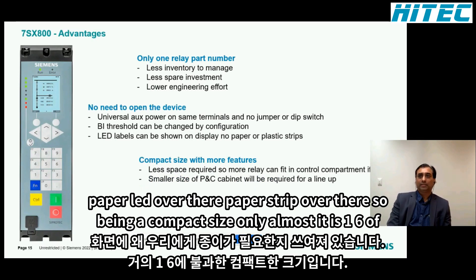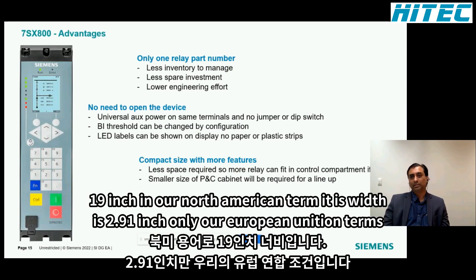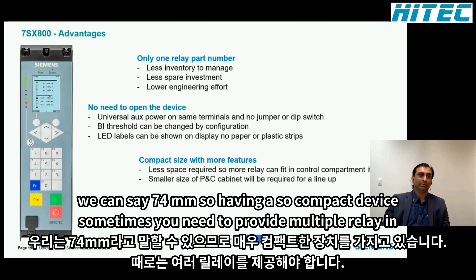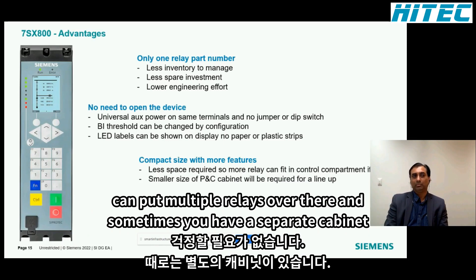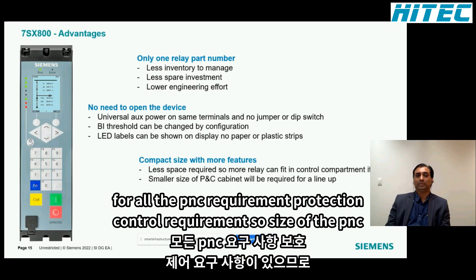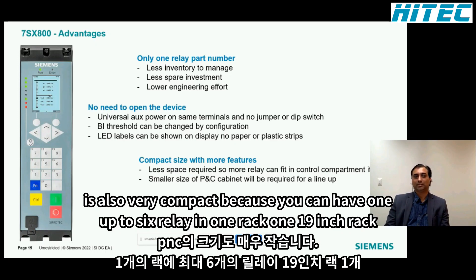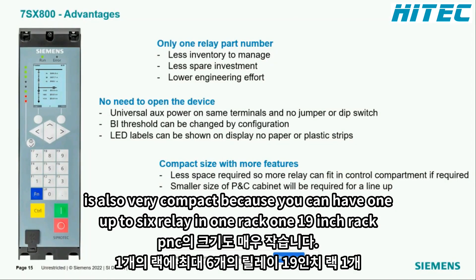Being compact — only about one-sixth of 19 inches, or 74mm wide (2.91 inches in North American terms) — allows multiple relays to fit in a medium voltage switchgear control chamber. For a separate protection and control cabinet, the compact size means you can fit up to six relays in a single 19-inch rack.